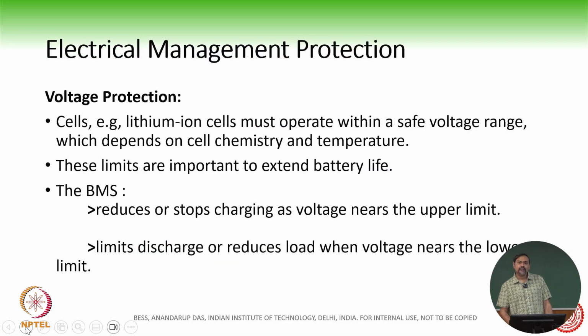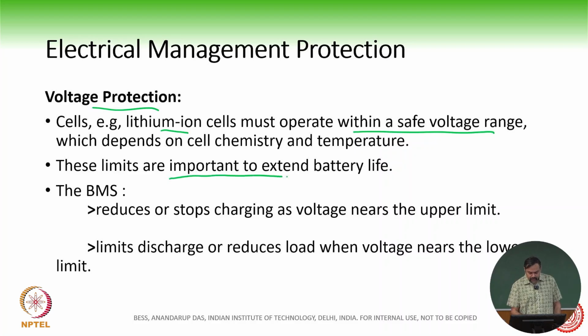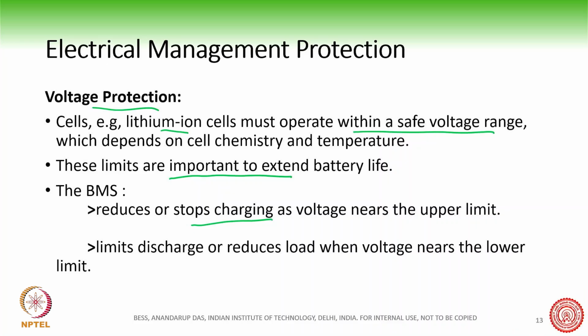Why are these important? Lithium ion cells must operate within a safe voltage range. These limits are important because if you cross them repeatedly, you degrade the battery life. So the BMS stops charging as the voltage nears the upper limit, or limits discharge when it nears the lower limit.